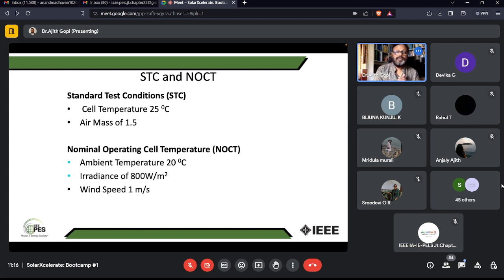That's why in Kerala kind of atmosphere, in summer, you will get 85 to 90% of output. For a 100 kilowatt plant, you can get 90 kilowatts. It is just because of the temperature loss. So because it is defined for 25 degrees centigrade, instead in real situation it works for 40 degrees centigrade, in our normal 30-degree ambient temperature.